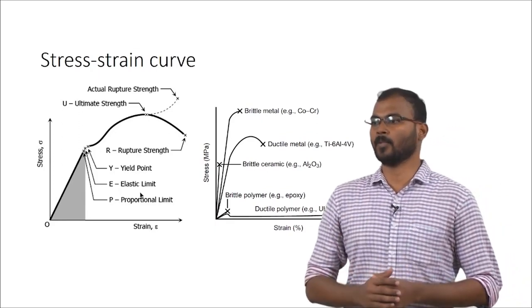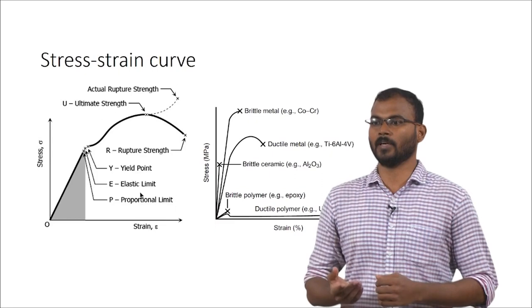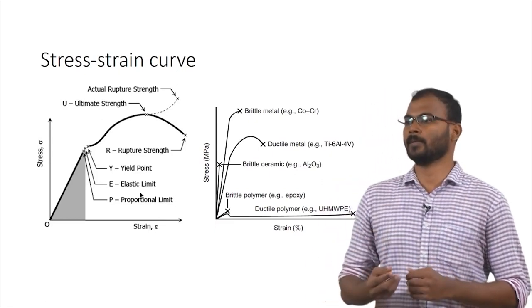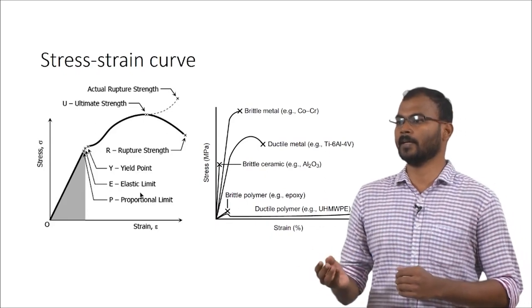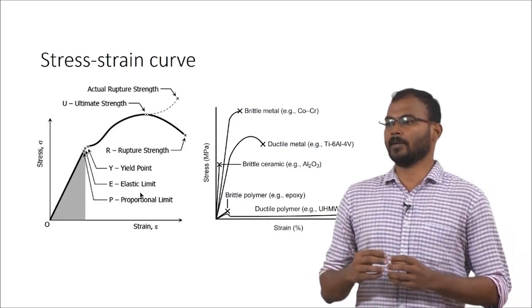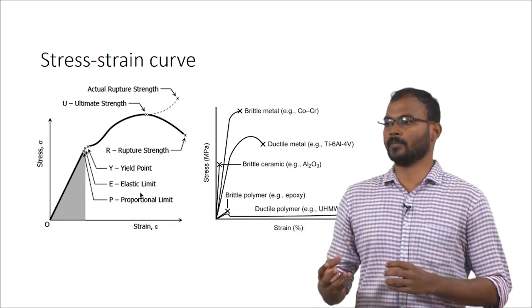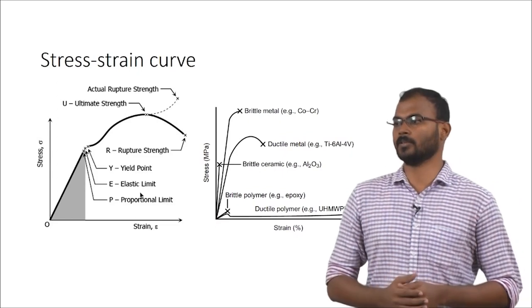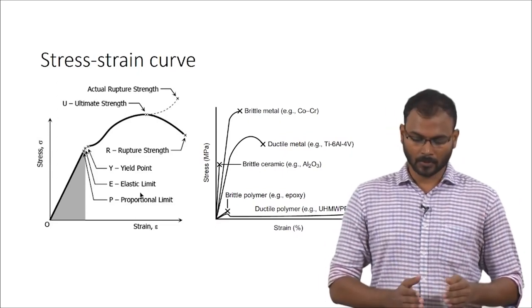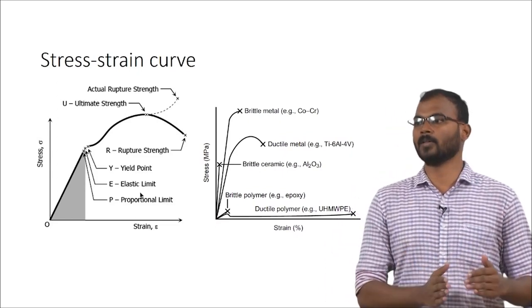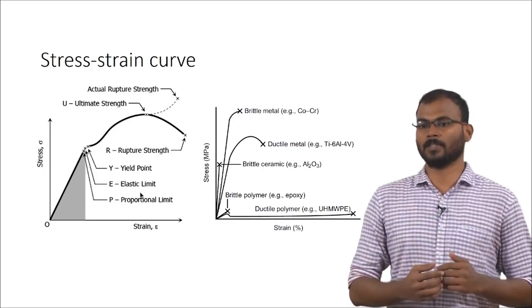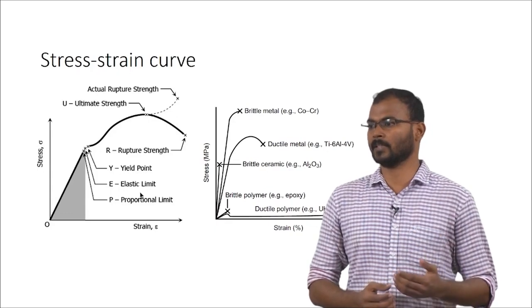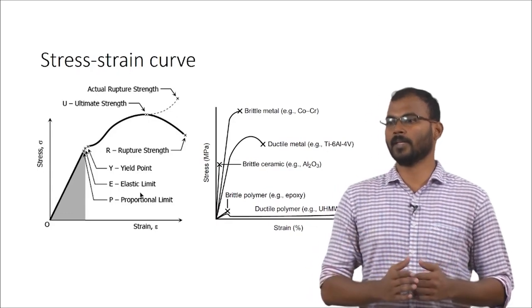For polymer materials used in vascular grafts and catheters, if the force applied goes beyond the yield point, its shape can change, which will cause problems when introduced into the biological system. Your material has to remain below that yield point — whatever force naturally occurs for that application should be below the yield point.